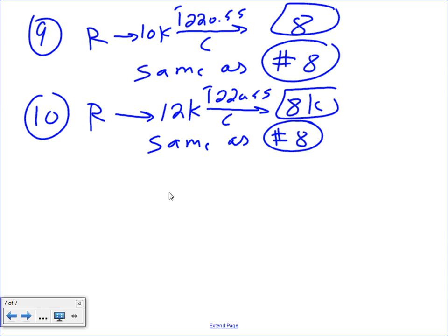Let's see if 11 is going to be the same. Take 11. Okay, I have a range. What's the range for 11? My 11 is 16.5 kW. Now you need to apply the table to 16.5. Hold your horses. When you apply the table, is this 12 or less? No, it's more than 12. So you're going to apply note number 1.